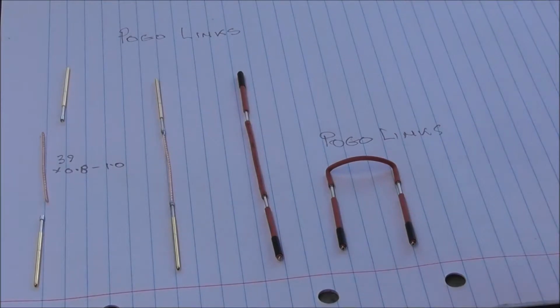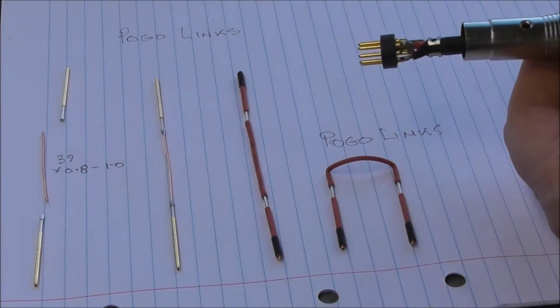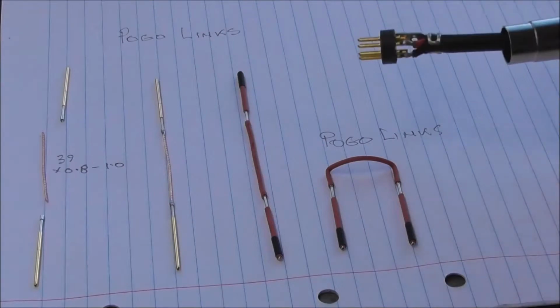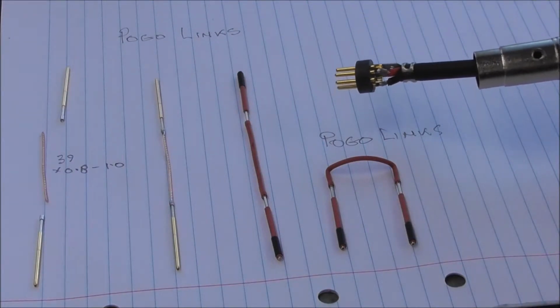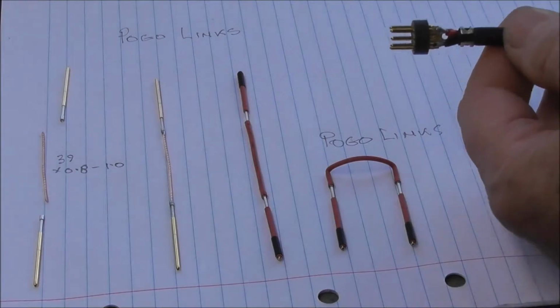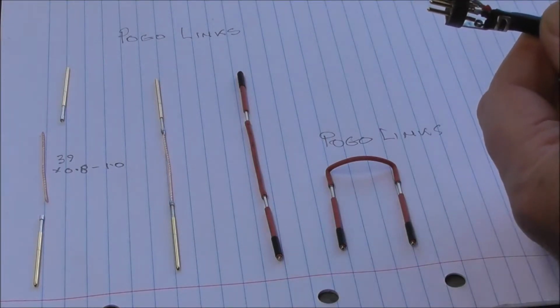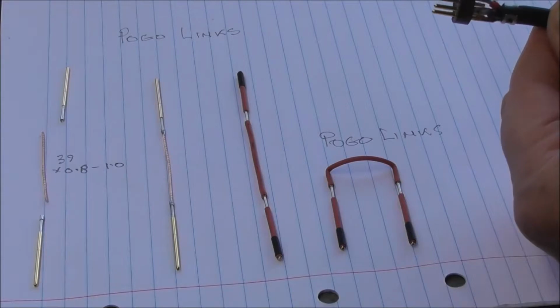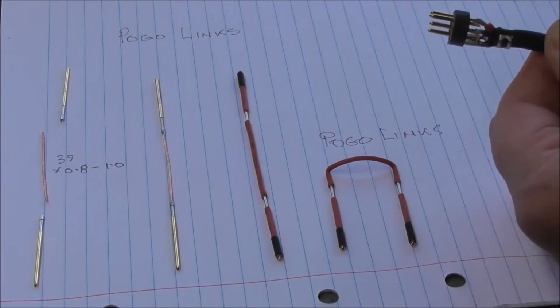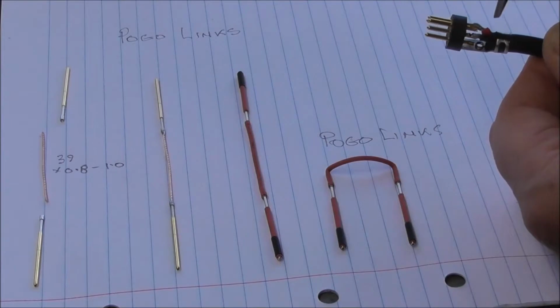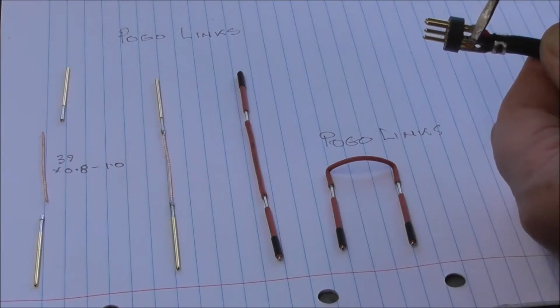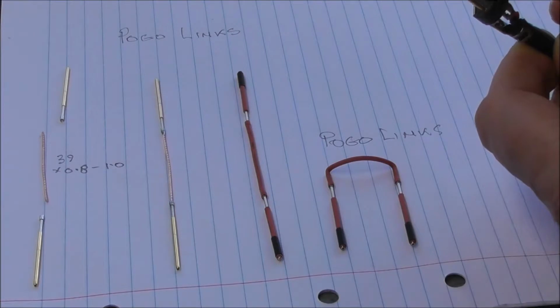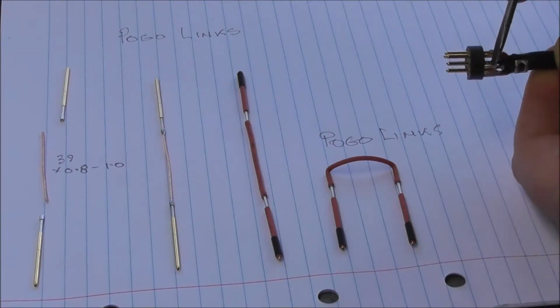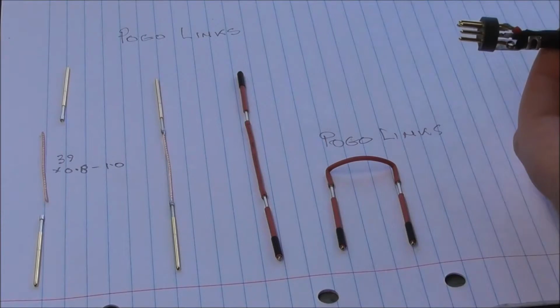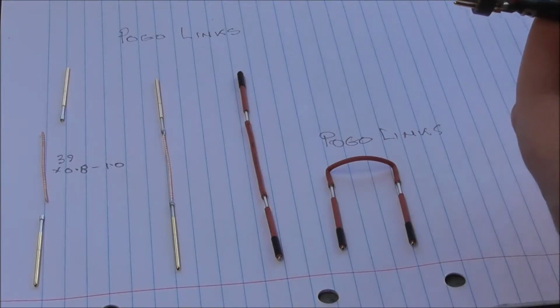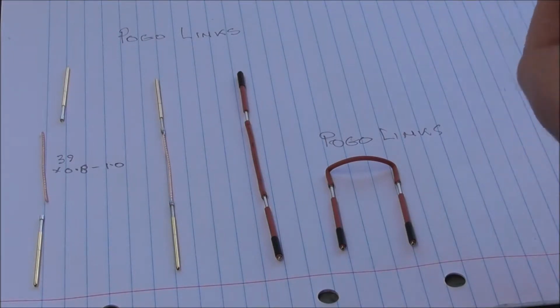Okay, let's go through the electrical wiring. You might want to change the main cable, for example if you want to fit a longer cable or a shorter cable. The plug is a 5-pin DIN plug, and it has connections to the 2 pins either side of center. So not the extreme pins and not the central pins, but the 2 pins either side of center. It can be a plus or minus connection. So it's just a 2-core cable connected through to that DIN plug.